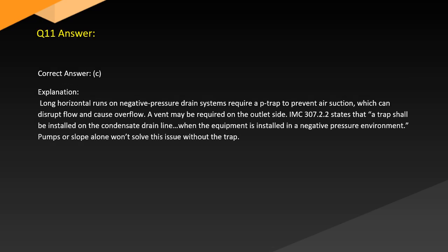Answer. Correct answer: C. Explanation: Long horizontal runs on negative pressure drain systems require a P-trap to prevent air suction, which can disrupt flow and cause overflow. A vent may be required on the outlet side. The IMC section 307.2.2 states that a trap shall be installed on the condensate drain line when the equipment is installed in a negative pressure environment. Pumps or slope alone won't solve this issue without the trap.